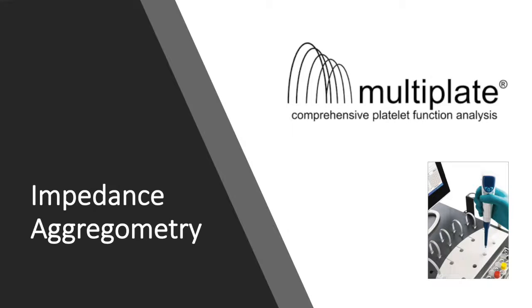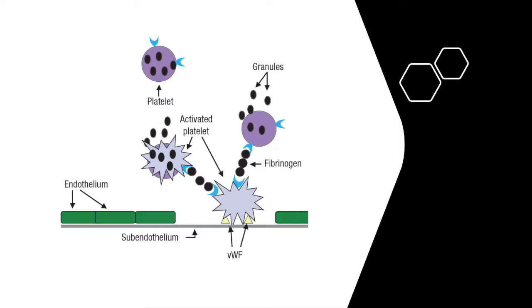Multi-plate impedance aggregometry is based on the principle that platelets are non-thrombogenic in their resting state, but expose receptors on their surface when they get activated, which allows them to attach on artificial surfaces.